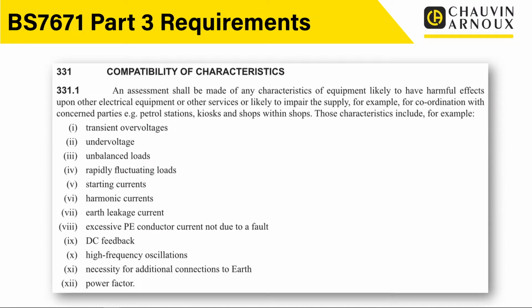Now, this one really ticks all the boxes in one go, and if you remember back to the first webinar in this series, we actually talked about the things that we look for when we do a power quality survey, and I think you'll see pretty much everything's on this list. So this is talking about compatibility of characteristics, and it says we should do an assessment of the characteristics of any equipment likely to have harmful effects on electrical equipment or other services, or likely to impair the supply. And if you look at what's included in here: transients, undervoltages, unbalanced loads, rapidly fluctuating loads, starting currents, harmonic currents. So all of these things we talked about, and down the bottom there we've got power factor. So these were topics that we talked about that are specifically related to power quality. So again, this section 331 is really driving us to the point where we need to know these things. We need to be able to quantify these things so that we can make the right decisions with regard to equipment and the installation and circuits and protective devices.